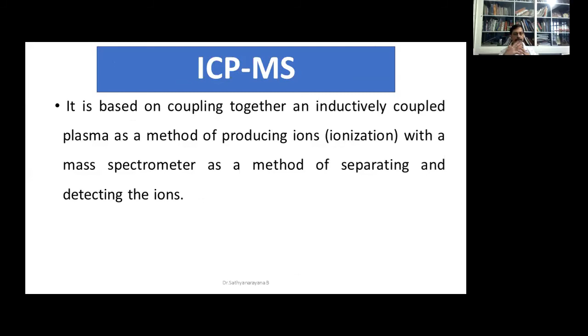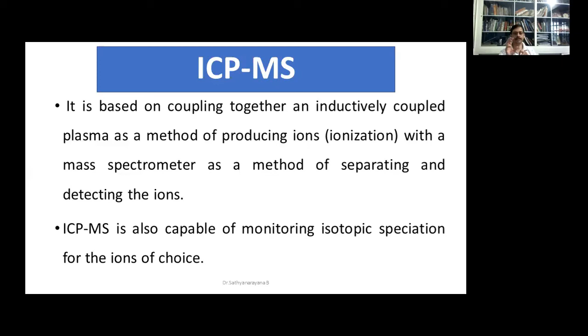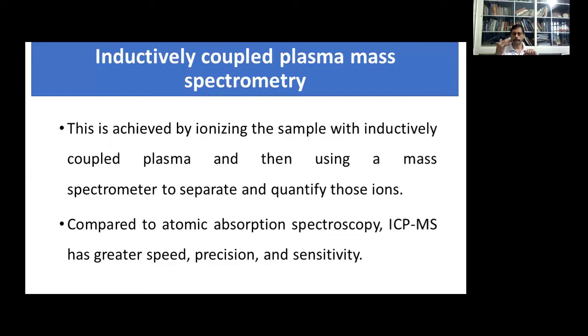This is very interesting. It may be the same chemical element, but maybe a different isotope. This isotopic speciation is not possible in technologies like atomic absorption spectroscopy or flame photometry. Here, we can even identify the isotopic speciation because mass to charge ratio is considered in mass spectroscopy. This is achieved by ionizing the sample with inductively coupled plasma and then using a mass spectrometer to separate and quantify these ions. Compared to atomic absorption spectroscopy, as I already mentioned, ICP-MS has greater speed, better precision, and high sensitivity.